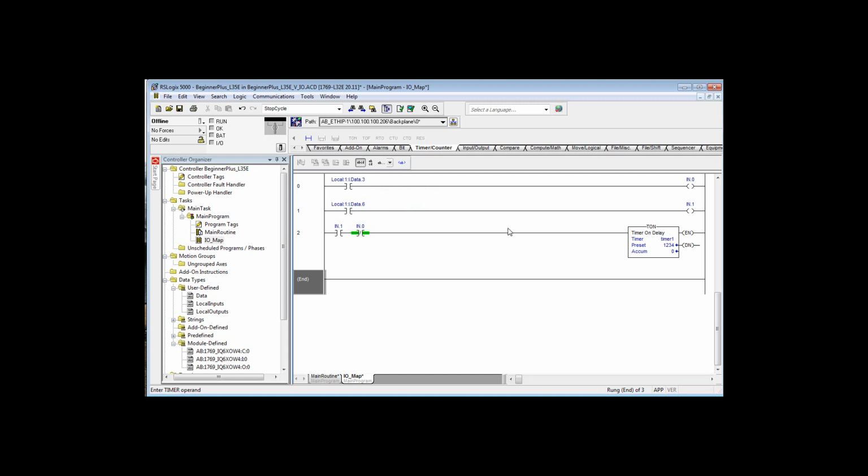Same thing here. And then let's say that this rung right here represents just the beginning of your logic, which goes on for a couple hundred rungs. Well, these two bits will follow whatever this is at the beginning of the program. In other words, at the beginning of the program, this rung is executed, and whatever bit 3 is here of that input module will set this bit to 1 or 0, and the same thing with bit 6. But the states of these two bits will not be visited again until it's all the way through the program and comes back and starts again. So you can rest assured, as you use these memory locations in your program, they won't change on the fly while you're executing the program.